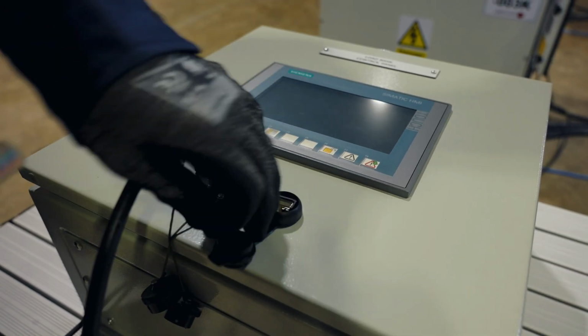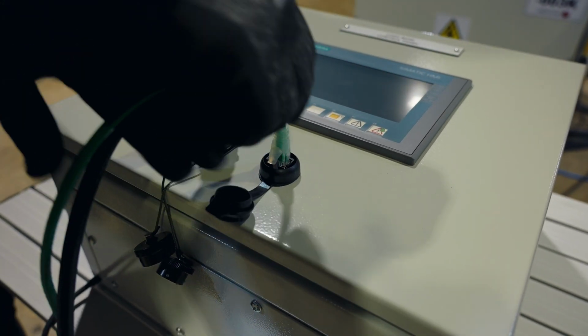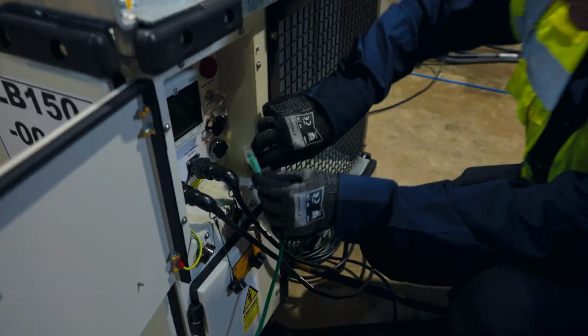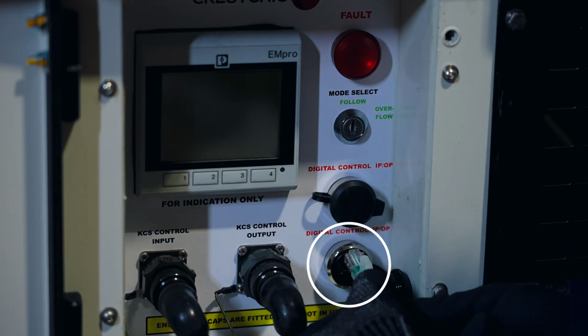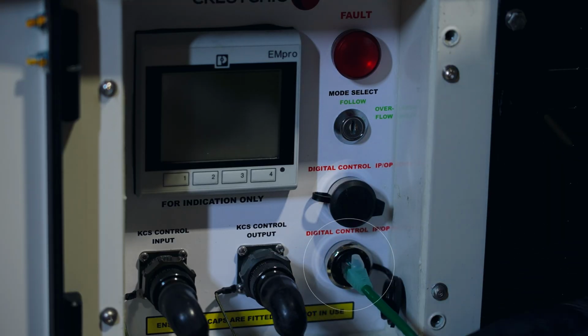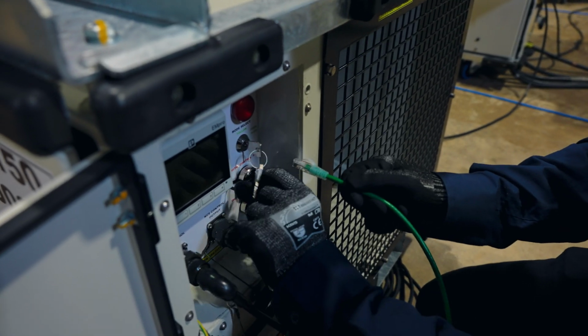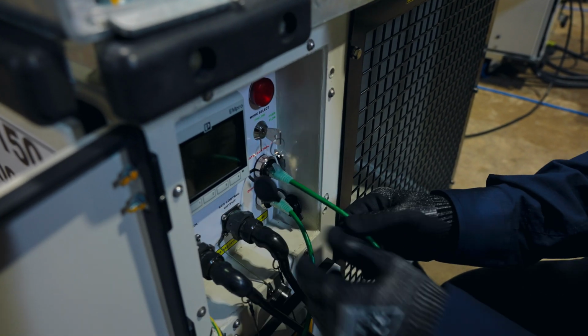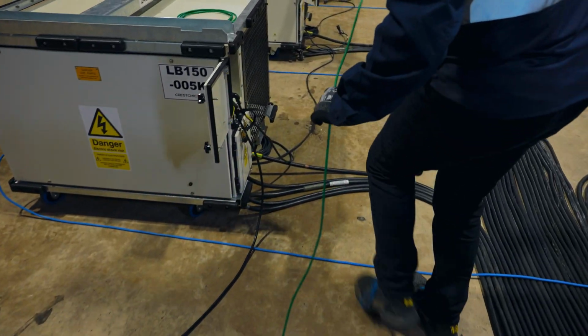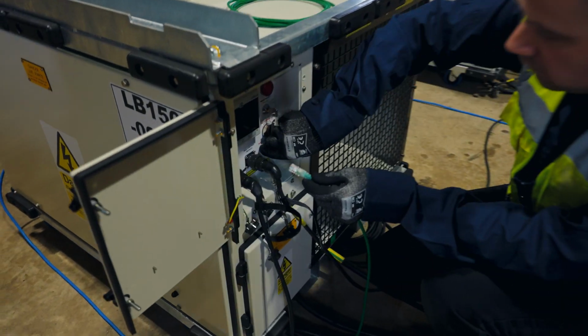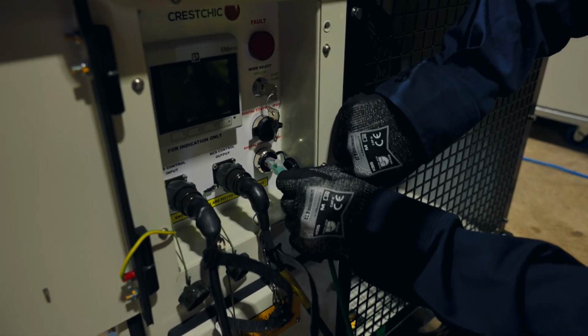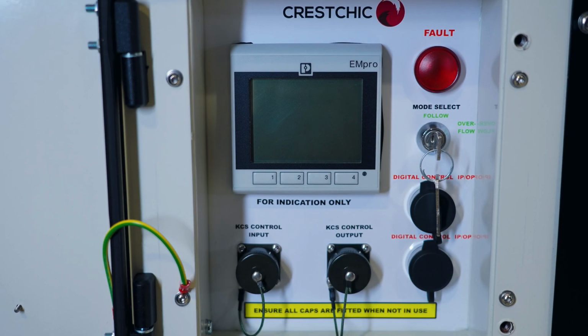Additional to this cable, an Ethernet cable also connects between the digital controller and the first load bank, and between all other load banks, using the digital control input-output sockets. The digital controller also requires an external control supply. Again, all control cables from the controller should be placed away from the load cables and the hot exhaust heat from the load banks. As previously explained, the load banks can be loaded in 2 different methods, follow and overflow.